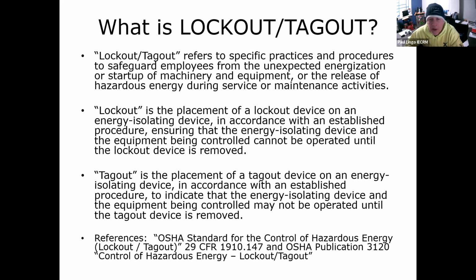We need to make sure we've got enough tag outs, so that depending on what it is we're locking and tagging, the circuit or the means of energy can be identified. It's vitally important that we do that. This is all OSHA practice, CFR 1910-147, so it's all referenceable within your OSHA standards.